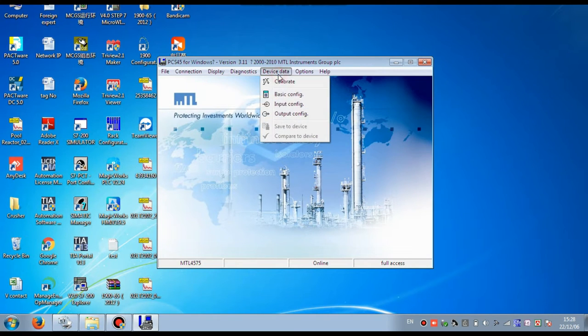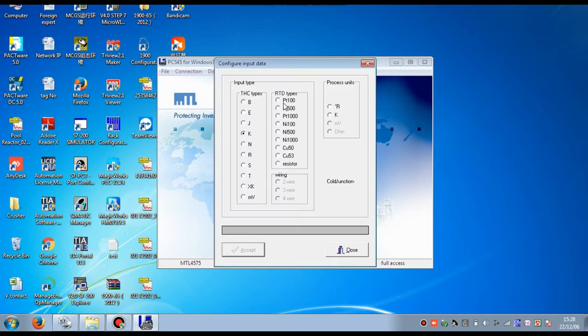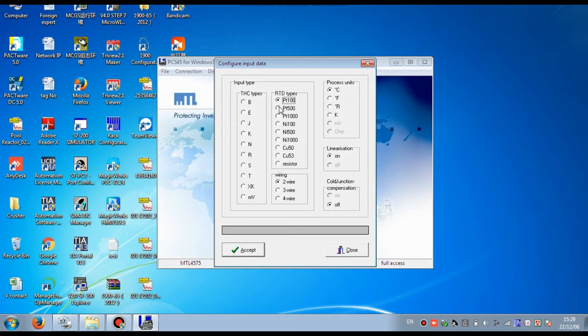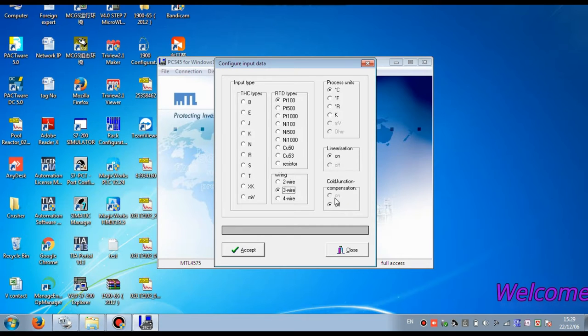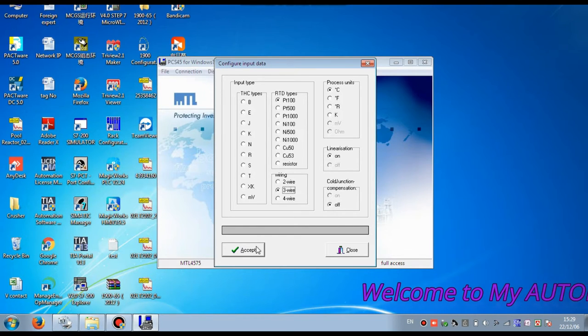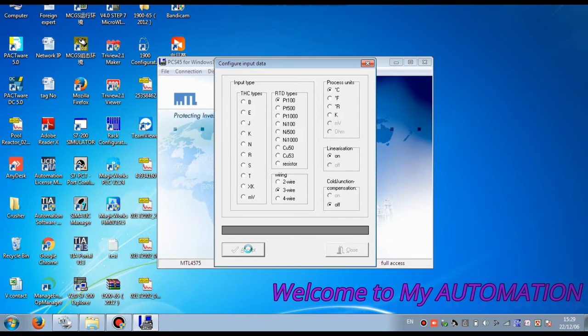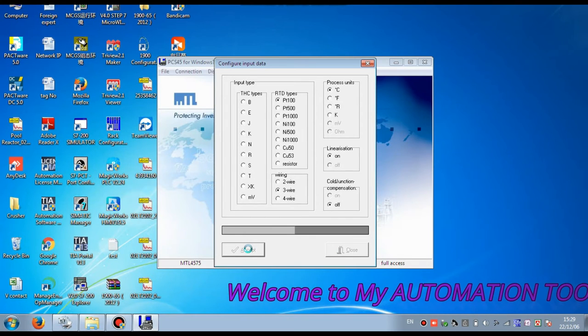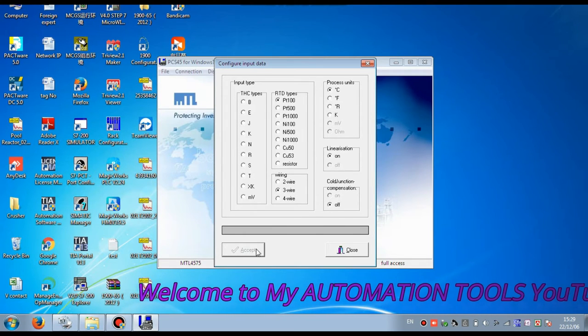Then go again to Device and press Input Configuration. Here we configure the sensor that we have already connected to the MTL. Our sensor is PT-100 and three-wire. You can see the PT-100 three-wire is selected, the process unit is degree Celsius, the cold junction is off. Press Accept to send all data to the MTL.